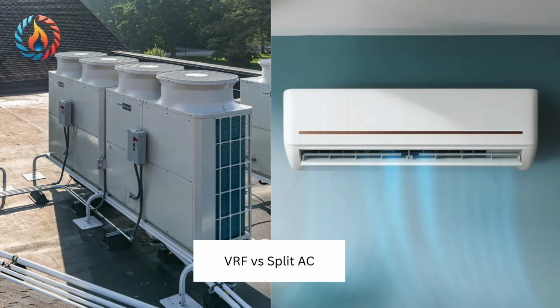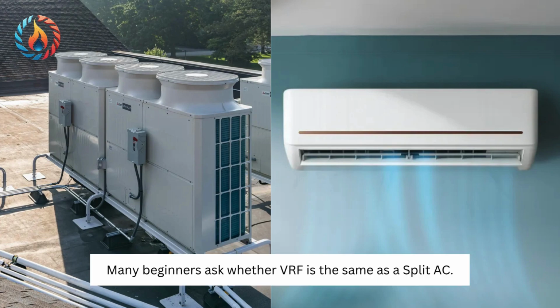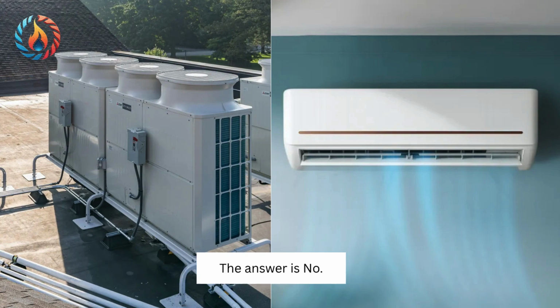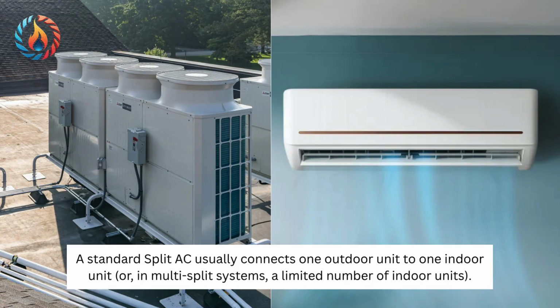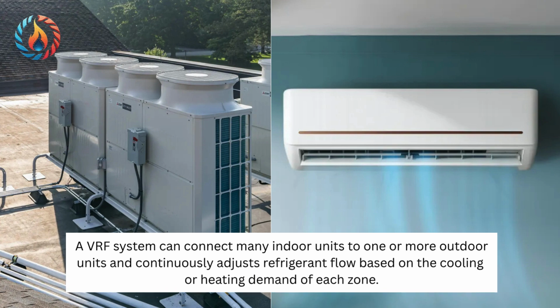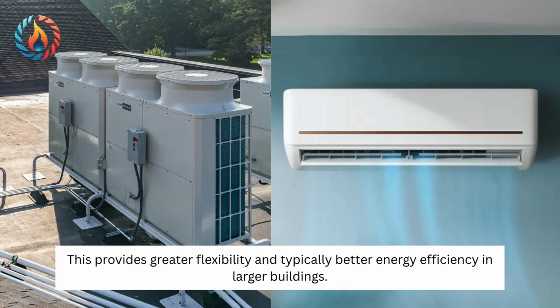VRF versus split AC. Many beginners ask whether VRF is the same as a split AC. The answer is no. A standard split AC usually connects one outdoor unit to one indoor unit, or in multi-split systems, a limited number of indoor units. A VRF system can connect many indoor units to one or more outdoor units and continuously adjusts refrigerant flow based on the cooling or heating demand of each zone. This provides greater flexibility and typically better energy efficiency in larger buildings.